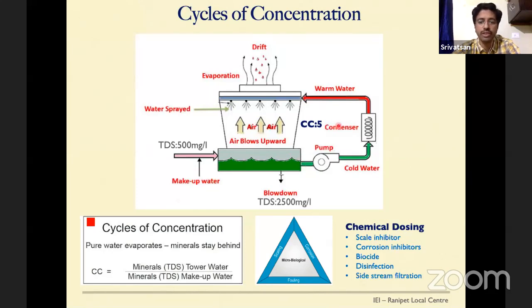Then for suspended solids removal, we go with a side stream filtration process. We take a portion of this cooling water cycle, treat it in a side stream filtration, and send it back to the cooling towers. In this cooling water cycle, around 90,000 meter cube of water is getting recirculated. However, we make up around 1,500 to 1,800 meter cube per hour of water. So by increasing the cycle of concentration, we are saving more water. Otherwise, if it's once through, you need to have 90,000 meter cube of water, which is not available anywhere.